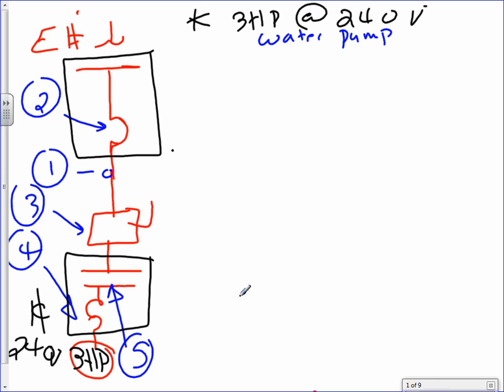Number 4 is the overload. If this pump gets overloaded for whatever reason, typically a malfunction in these pumps, do you want the pump to burn, or do you want the overload to trip to give you an idea, hey, go maintain that pump before it burns, right? That's what the overload is. Any comments, any questions about these 5 very important things that we need to size for any pump? Can I have a thumbs up, Chad? Yeah, we got it? Okay. The first thing, guys, I want to start with number 1. Number one is called, and you guys know that, branch circuit conductors.